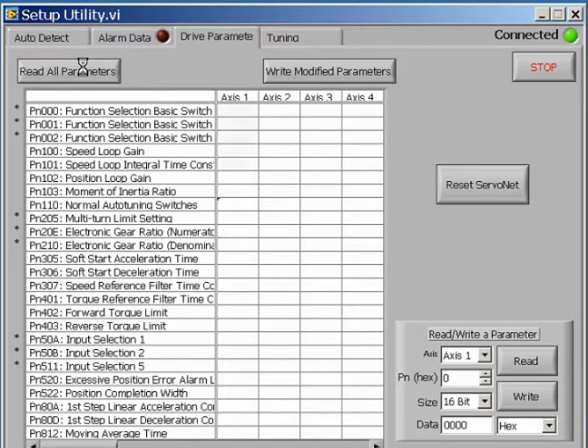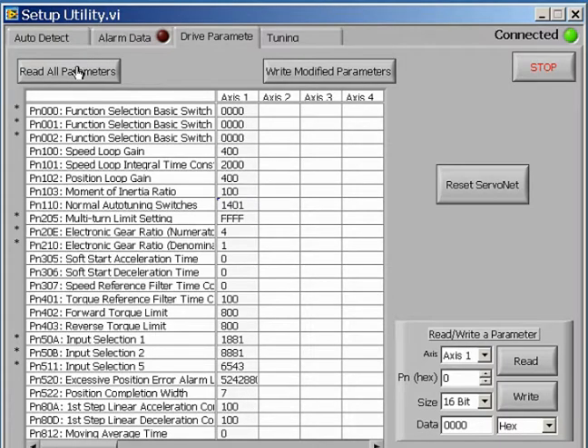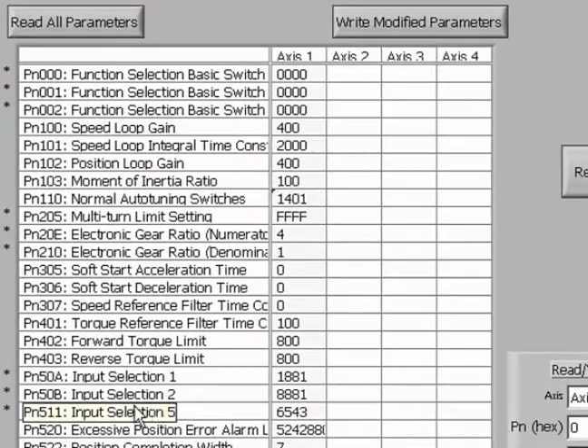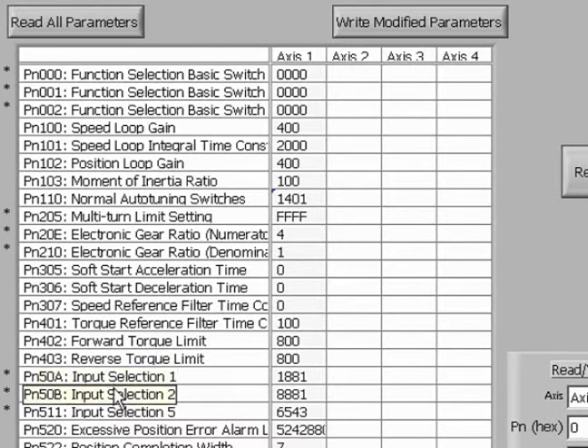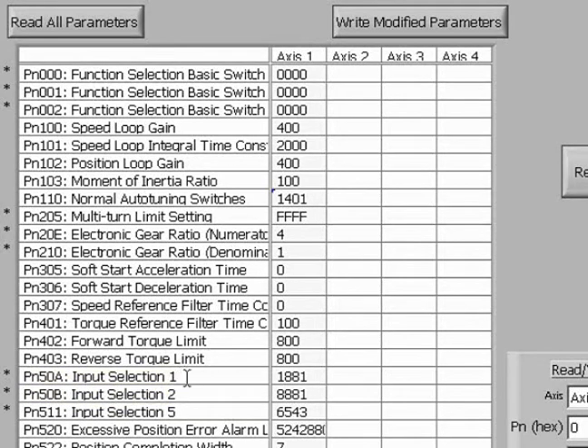We read all parameters, which will populate the data fields for the servo drive. Let's look at 50A, Negative Over-Travel, and 50B, Positive Over-Travel. To disable over-travels, we click on the 50A data cell and change it to 8881.